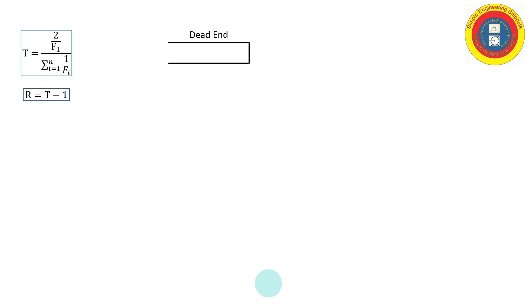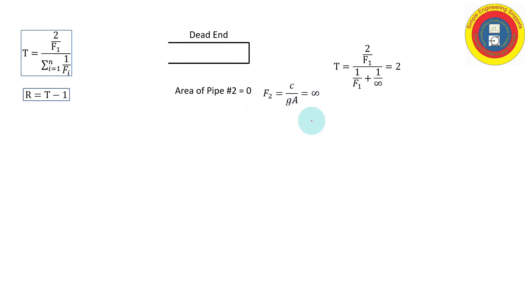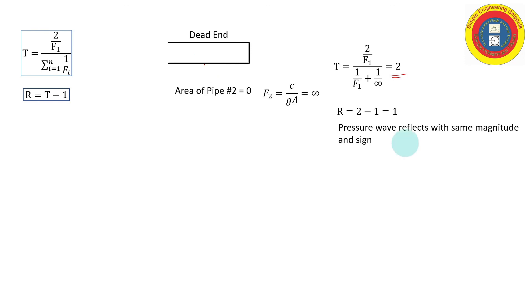Let's look at special cases. For a dead end, nothing is transmitted past it. Setting the area of pipe two to zero makes its elastic factor infinity. The transmission factor becomes T equals two over F1 divided by one over F1, which equals two. Therefore the reflection factor R equals one: an incoming wave reflects off a dead end with the same magnitude and same sign.